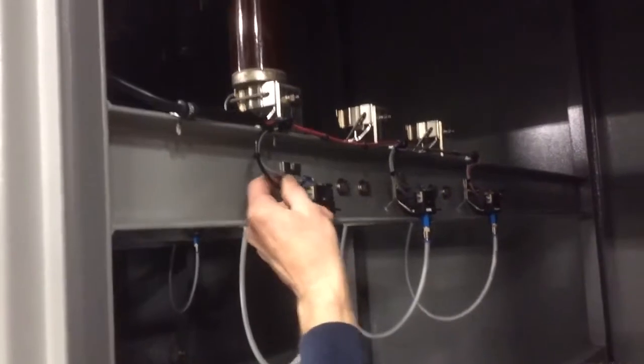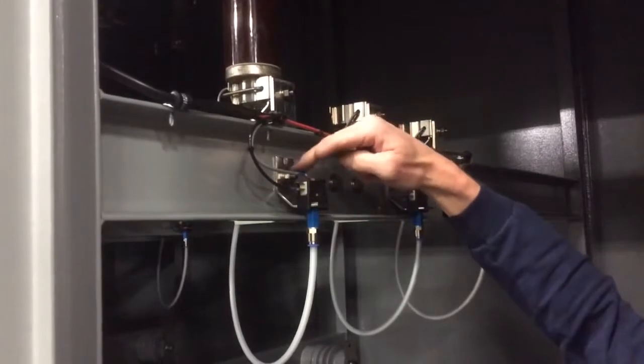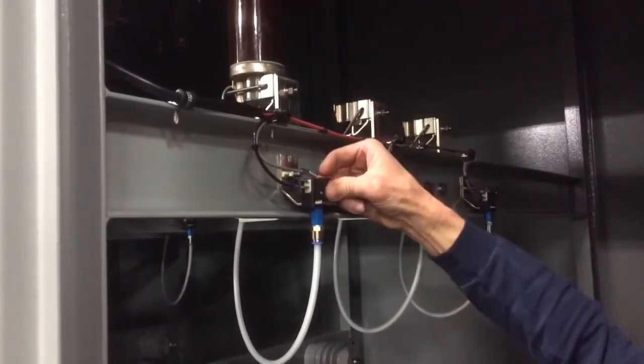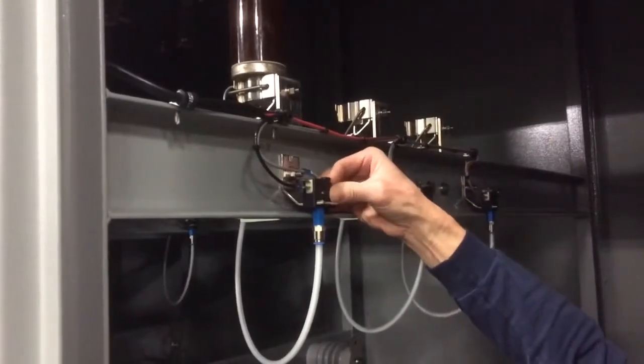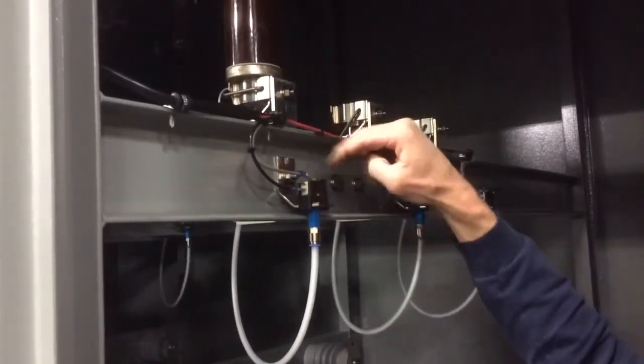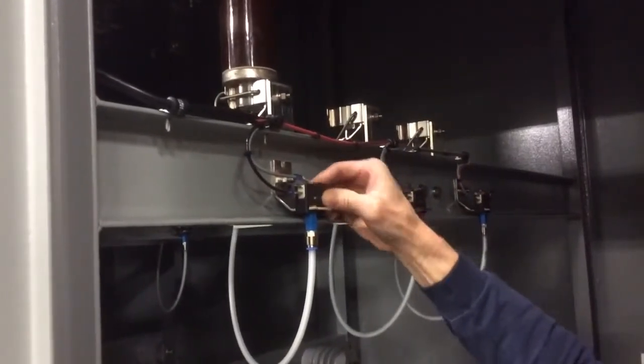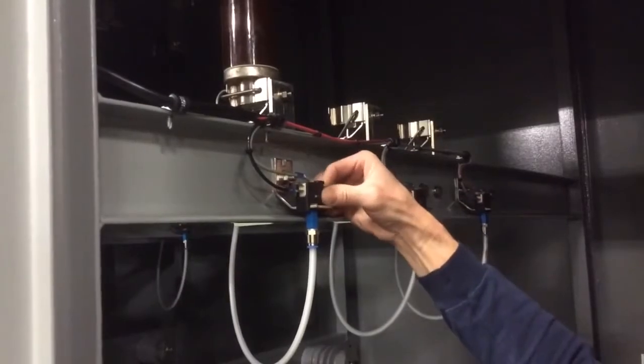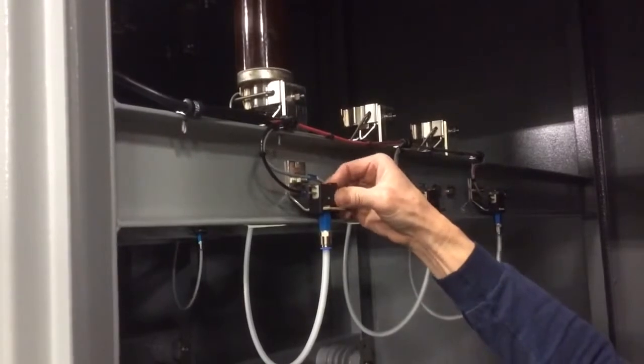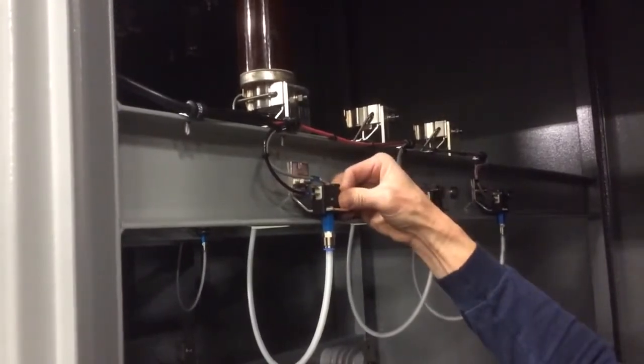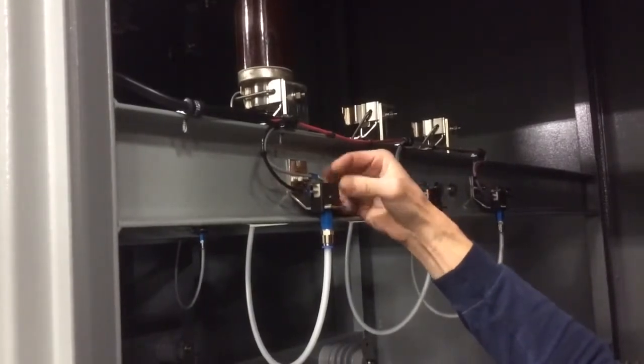Typically the switch is connected in a normally closed configuration, which would be the two outside terminals of the micro switch. The reason for that is we usually run a series circuit with voltage applied to one terminal. When the switch operates, it opens the circuit. That being the case, you need to be aware that there could be voltage on either of these terminals at any time. Make sure you disconnect the source when working on the system.